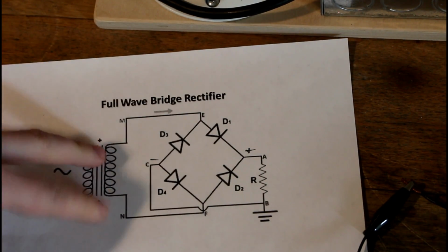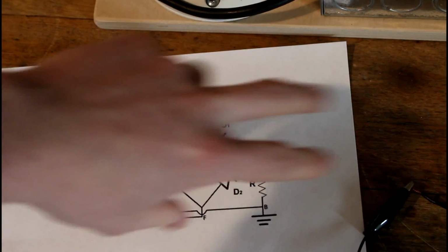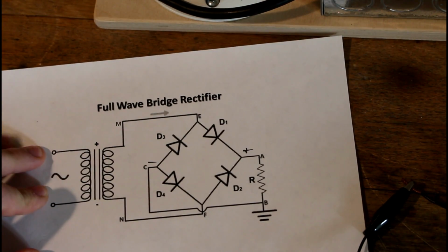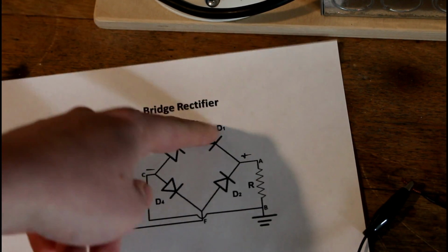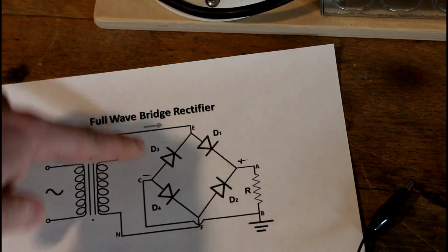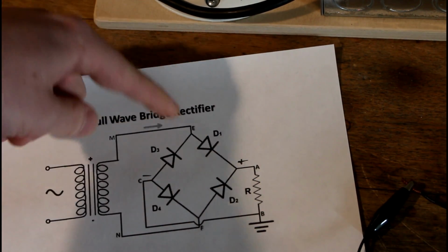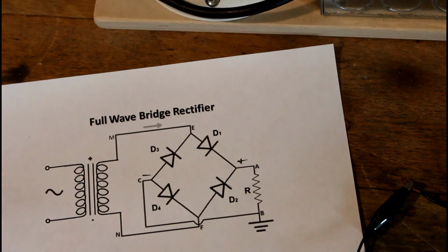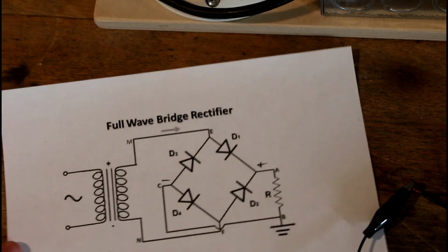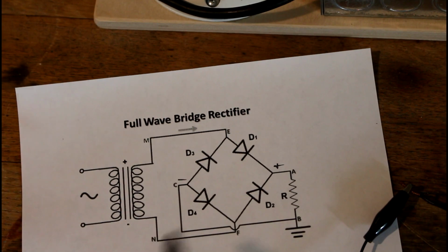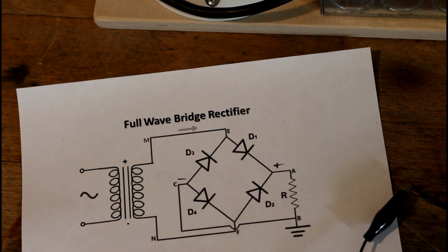Because the transformer electrically isolates everything on the rectifier side and beyond from your mains input, it's perfectly fine to reference any of these points to earth. You could call this ground, or this down here ground, this input ground — it doesn't matter, because there's no electrical connection through here to ground anywhere.